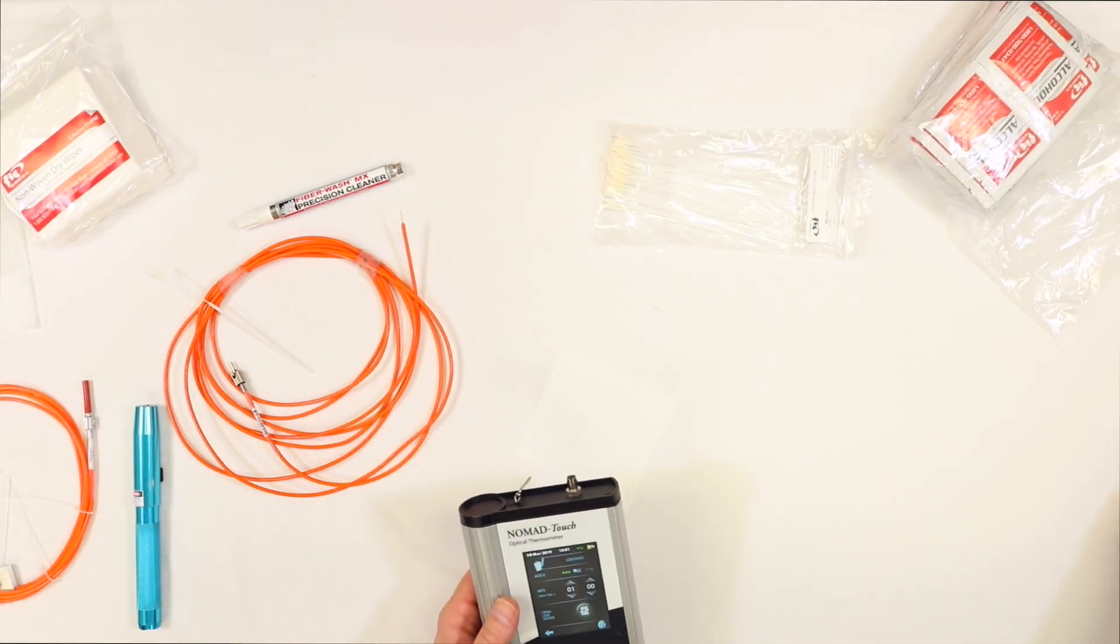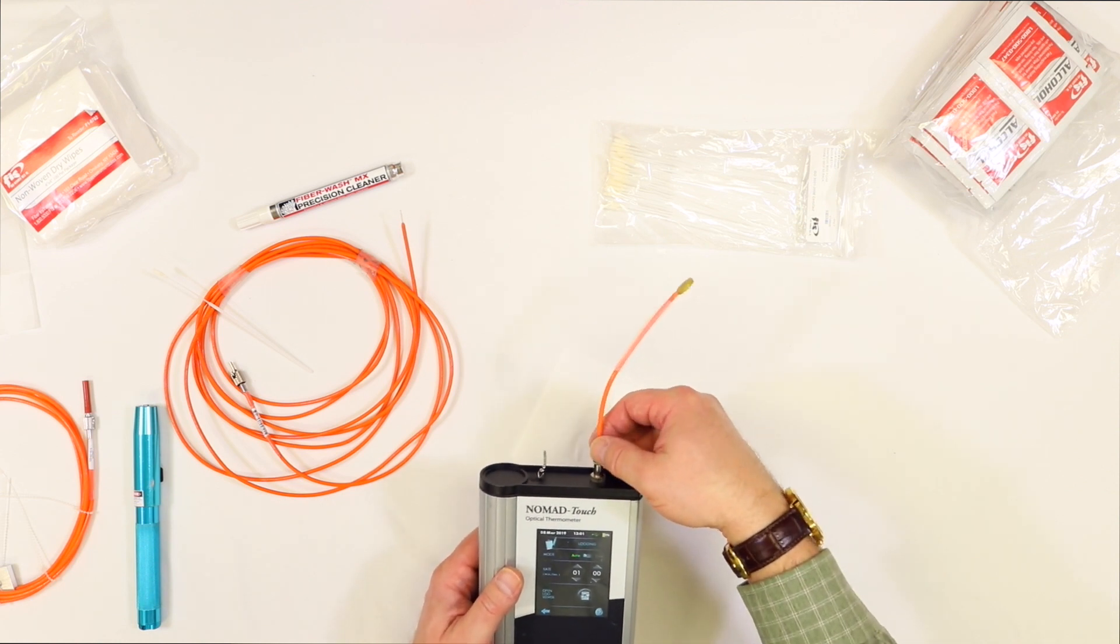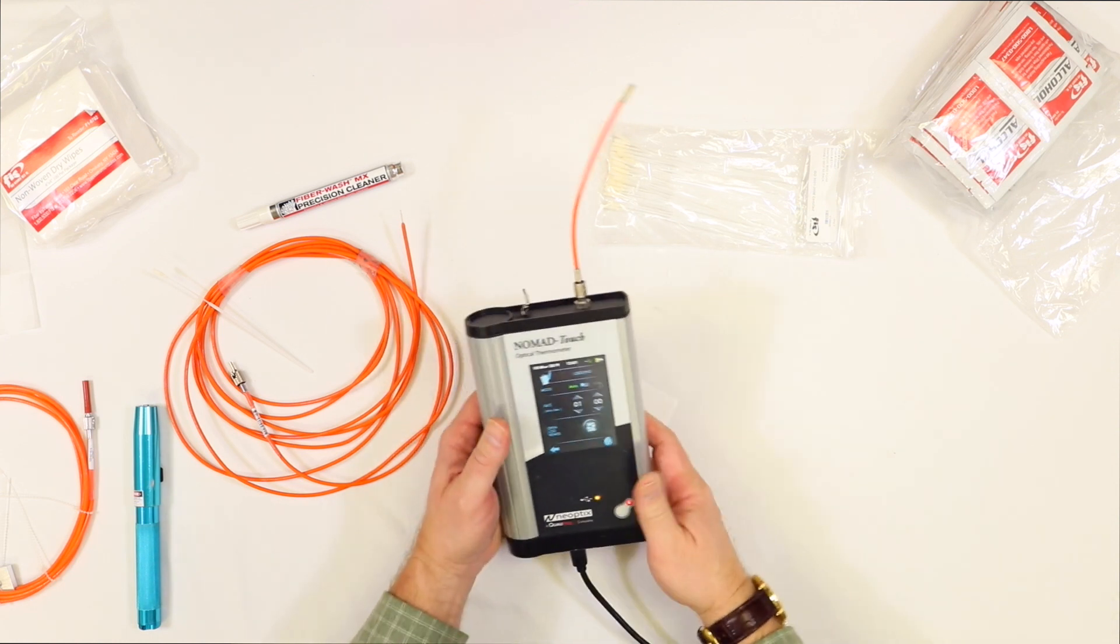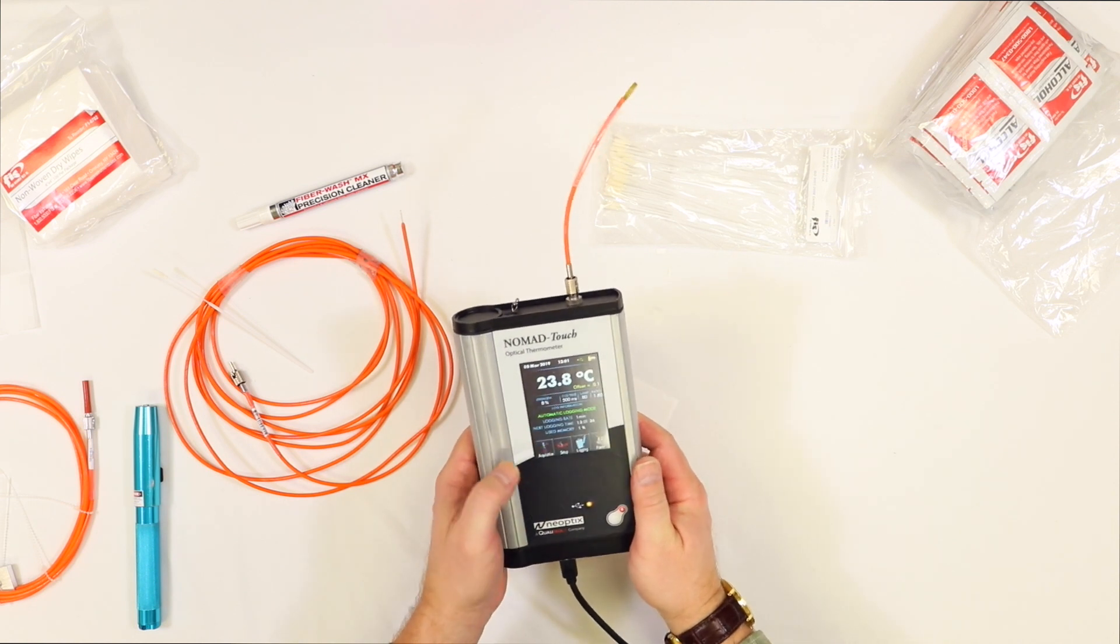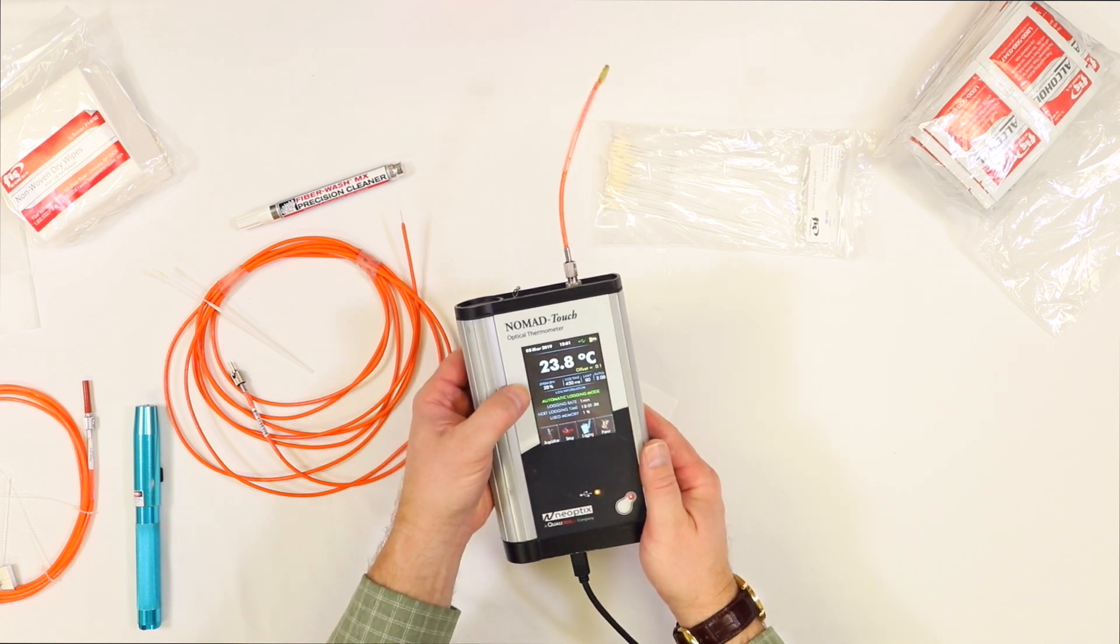Now we've cleaned a fiber previously. This was running at about 7% efficiency. And now with the cleaning, we're at about 28% signal strength instead of the 7% that we originally started at.